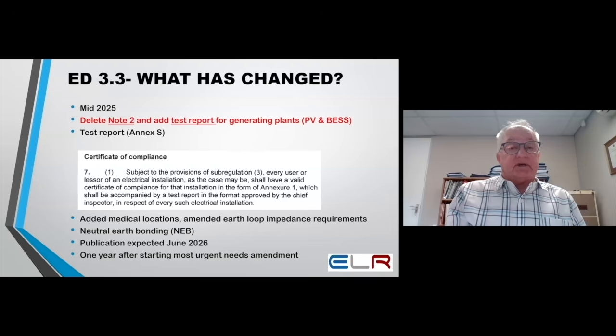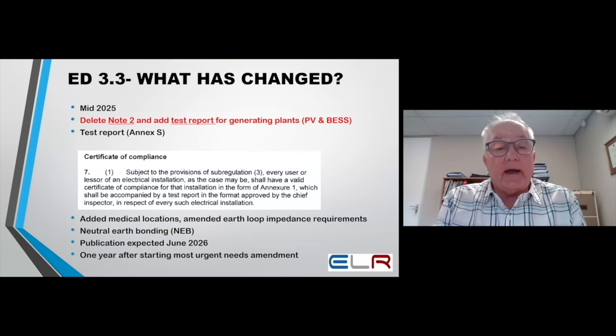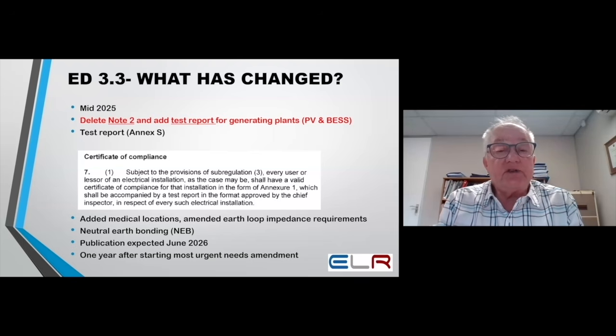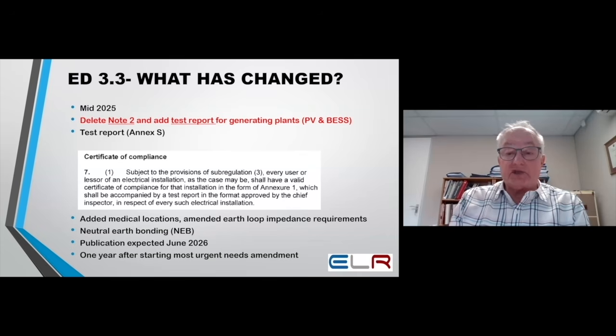The test report, in terms of the EIR or installation regulations, shall have - every user or lessor of an electrical installation shall have a valid certificate of compliance for that installation in the form of Annexure 1 in the EIR, which shall be accompanied by a test report in the format approved by the Chief Inspector in respect of every such electrical installation.